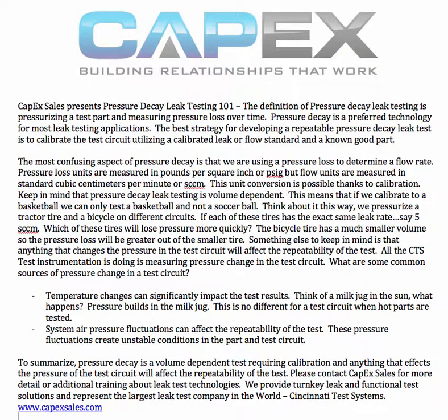Any pressure fluctuations of test circuits, of cylinders, of the system in general, could create some repeatability issues. And they're very difficult to track down. So that could be a problem if you're suffering from repeatability issues.